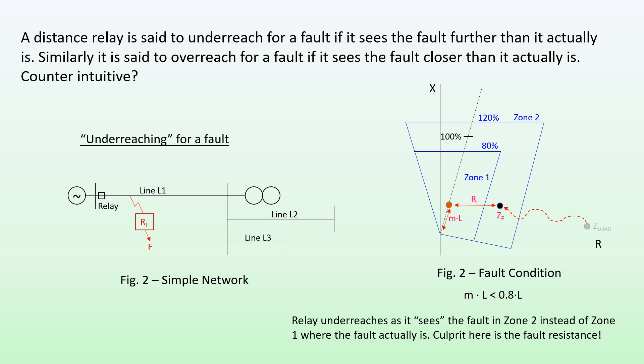The distance from the origin to the apparent fault location Zf is now bigger than from the origin to where the fault should have been. So the relay sees the fault further than it actually is, and therefore for this fault condition we say the relay has under-reached. The relay under-reaches as it sees the fault in Zone 2 instead of Zone 1, and the culprit here is the fault resistance.